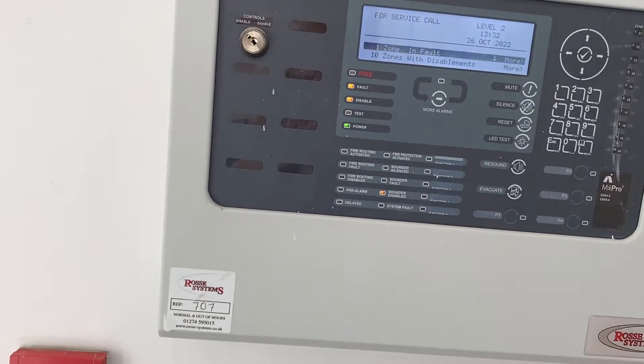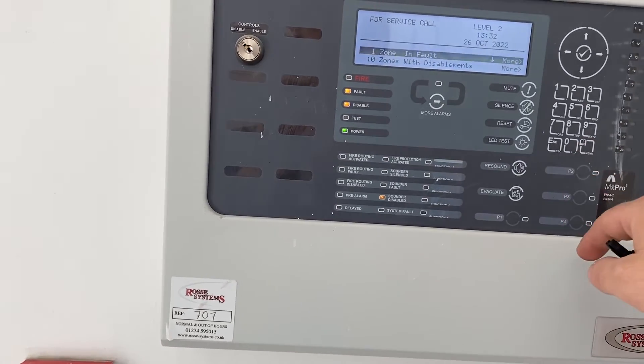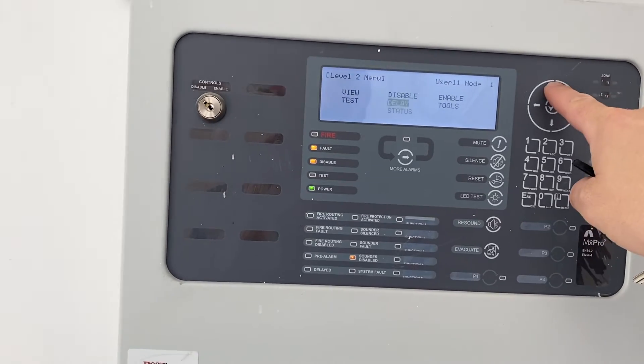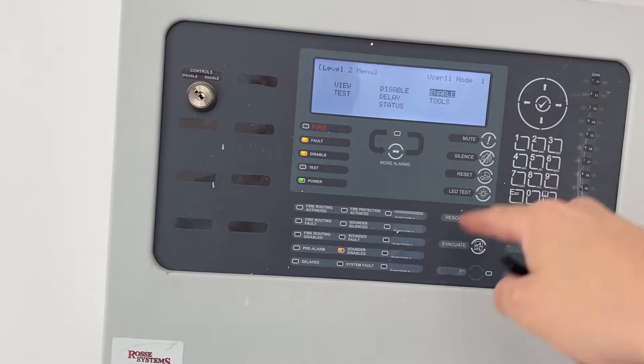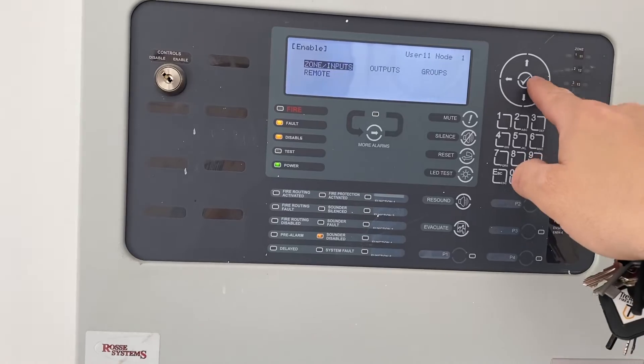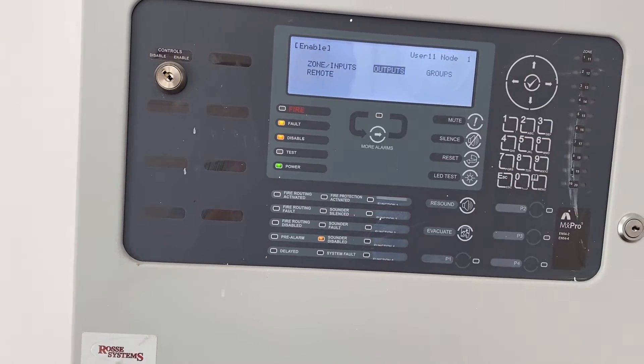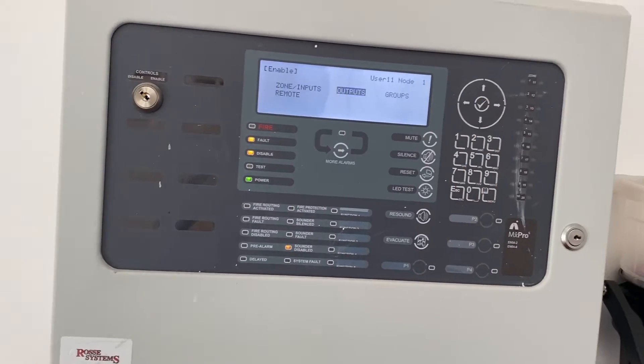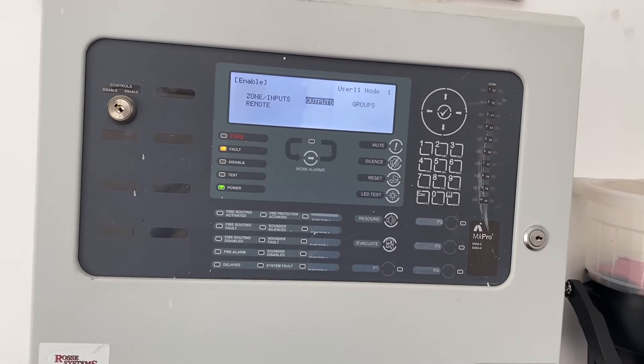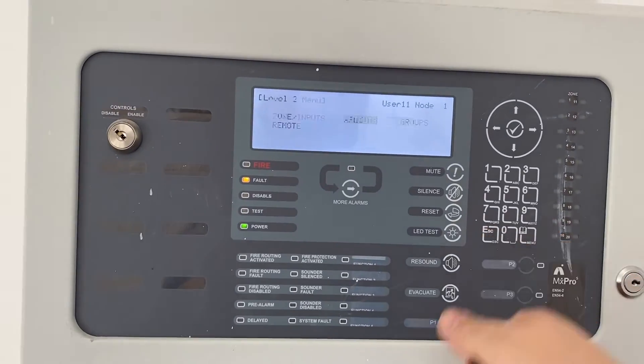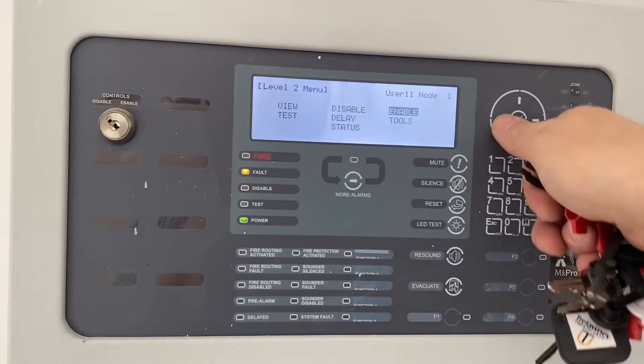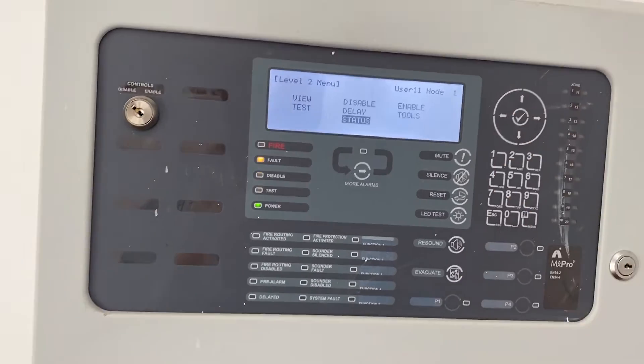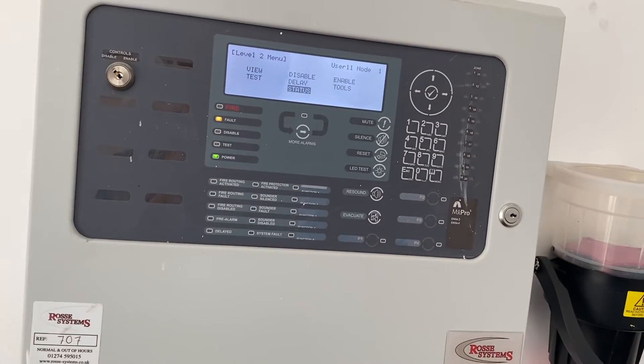You'd have to hit reset there per device. To re-enable once you're finished, go into menu and this time to enable. Into outputs and turn on all sounders. All your lights go off. There is a fault on this panel so the fault light will remain. Go back to status to clear the status light.